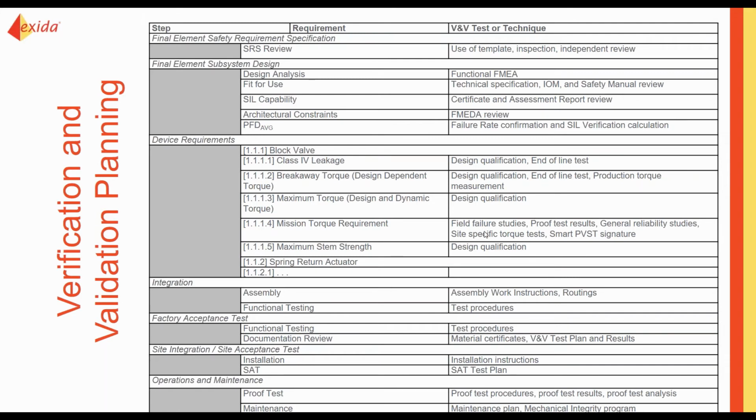Mission torque requirement, that is probably not going to, that cannot come completely from the OEM. That's going to have to come from understanding, as an end user, what you've got in the field. Is your process reacting with the materials? Do you see things change over time? So field failure studies, proof test results, as we get more specific generic reliability studies, we can probably start giving some guidance on that, but that's an area that needs some focus. So likewise, in the device, any requirement is going to have to be validated.